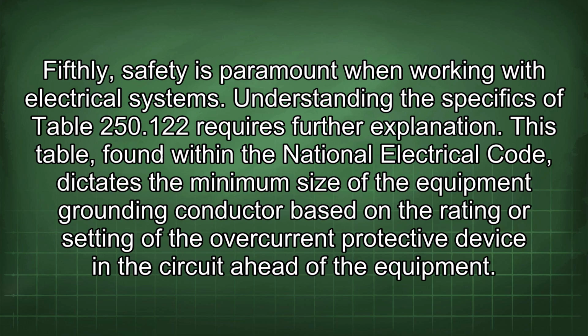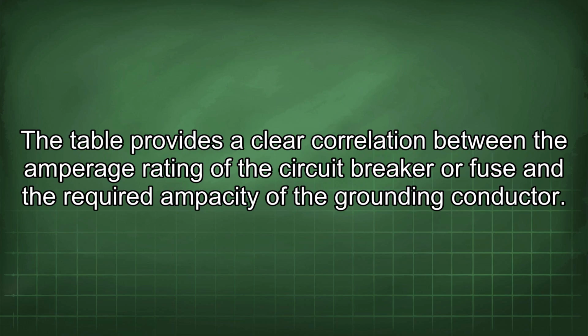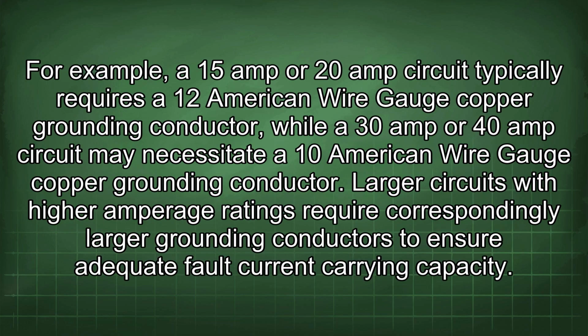Understanding the specifics of Table 250.122 requires further explanation. This table, found within the National Electrical Code, dictates the minimum size of the equipment grounding conductor based on the rating or setting of the overcurrent protective device in the circuit ahead of the equipment. The table provides a clear correlation between the amperage rating of the circuit breaker or fuse and the required ampacity of the grounding conductor. For example, a 15 amp or 20 amp circuit typically requires a 12 American wire gauge copper grounding conductor, while a 30 amp or 40 amp circuit may necessitate a 10 American wire gauge copper grounding conductor. Larger circuits with higher amperage ratings require correspondingly larger grounding conductors to ensure adequate fault current carrying capacity.